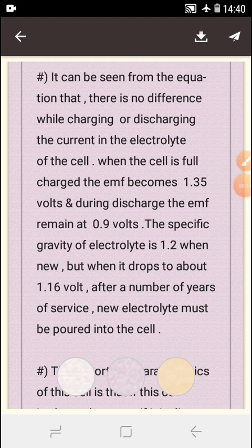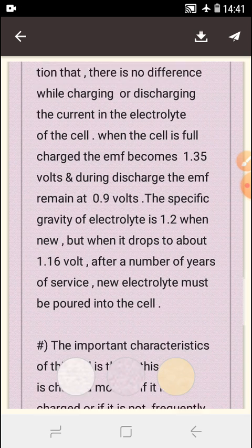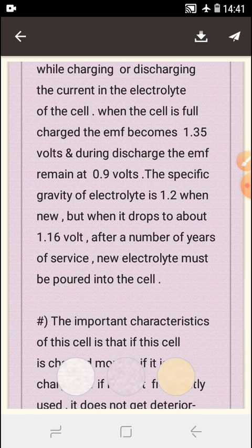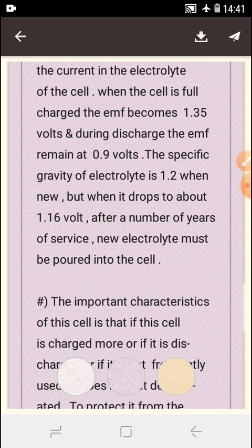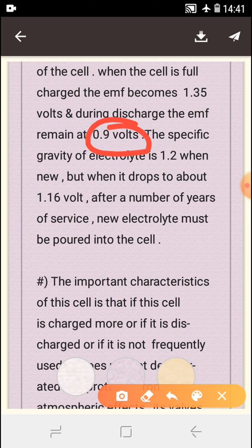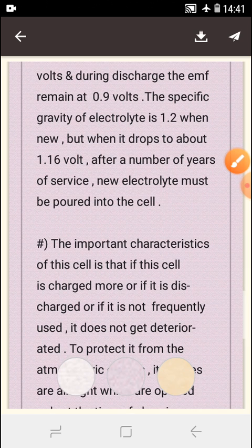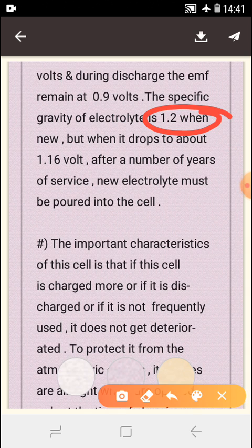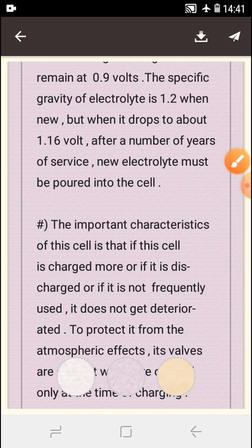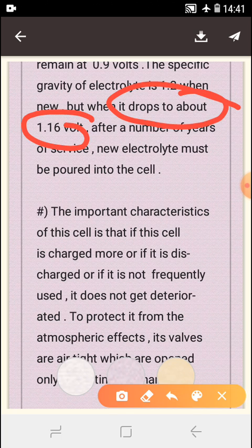It can be seen from the equation that there is no change in the electrolyte while charging or discharging. When the cell is fully charged, the EMF becomes 1.35 volts. During discharge, the EMF remains at 0.9 volts per cell. The specific gravity of the electrolyte is 1.2, but when it drops to about 1.16, attention is required.